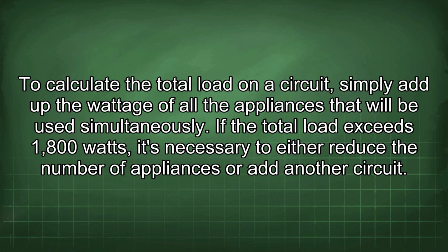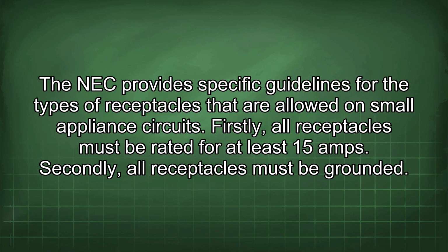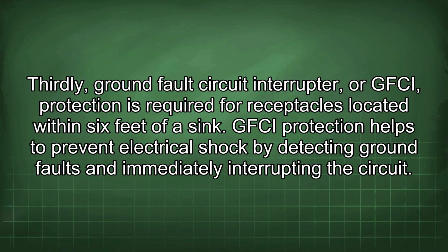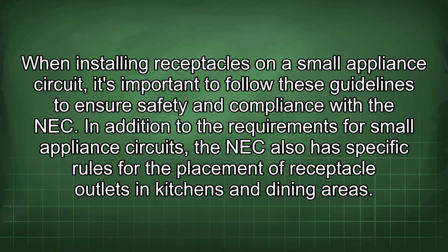The NEC provides specific guidelines for the types of receptacles that are allowed on small appliance circuits. Firstly, all receptacles must be rated for at least 15 amps. Secondly, all receptacles must be grounded. Thirdly, ground fault circuit interrupter, or GFCI, protection is required for receptacles located within 6 feet of a sink. GFCI protection helps to prevent electrical shock by detecting ground faults and immediately interrupting the circuit. When installing receptacles on a small appliance circuit, it's important to follow these guidelines to ensure safety and compliance with the NEC.